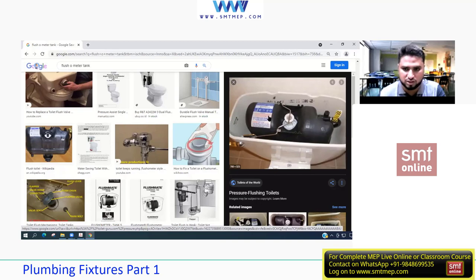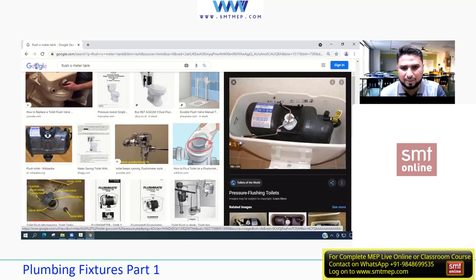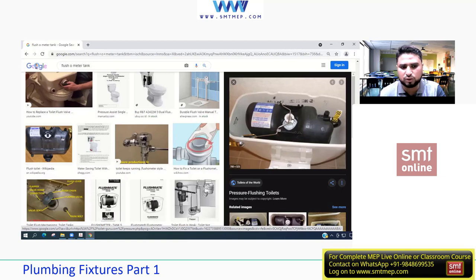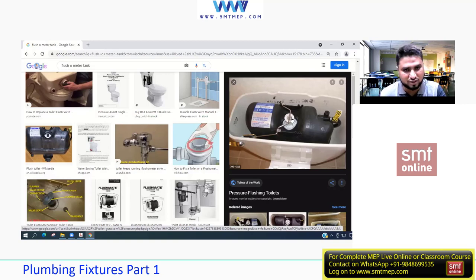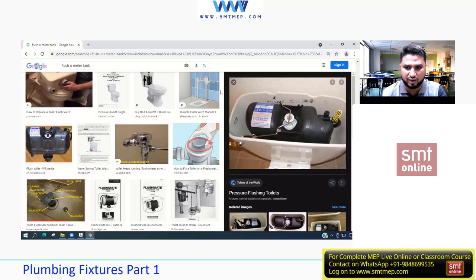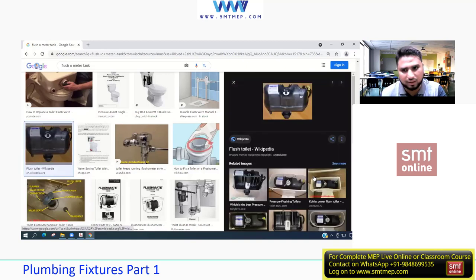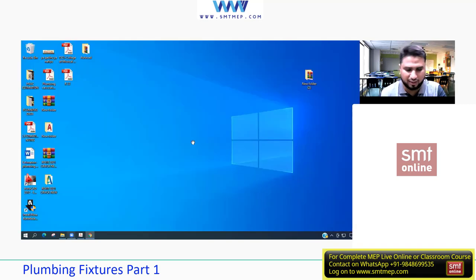In the flushometer tank, when you press the knob, it acts on a lever that lifts and releases pressure from the air accumulator, expelling both water and compressed air simultaneously. This makes it more effective than a normal gravity flush tank. It is more expensive due to this air-pressure system, but provides more efficient cleaning.